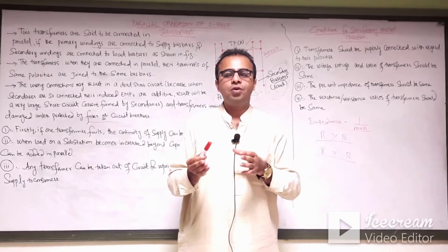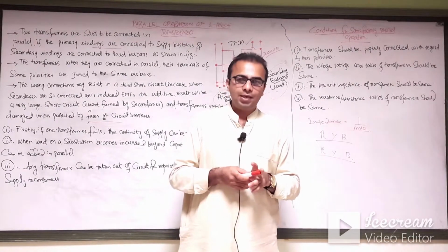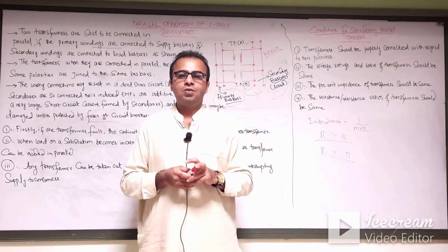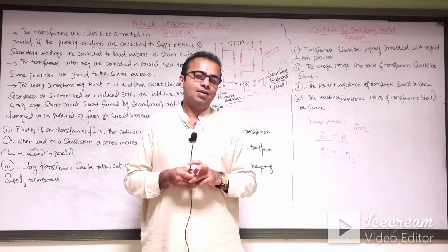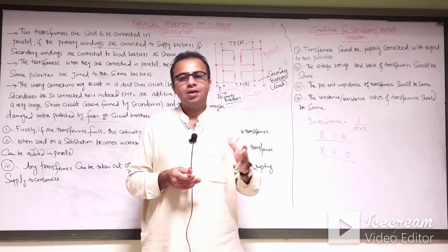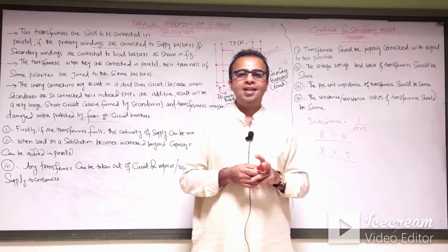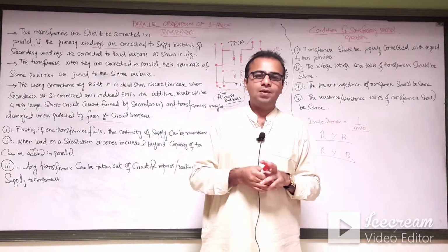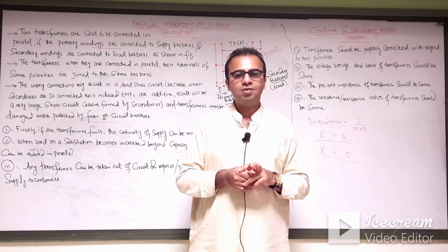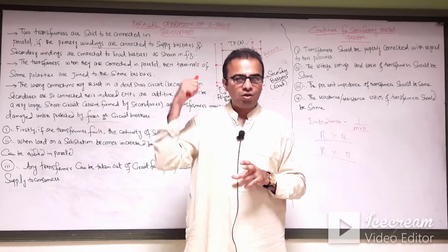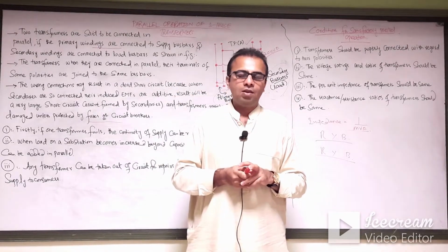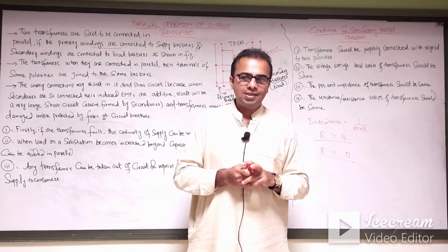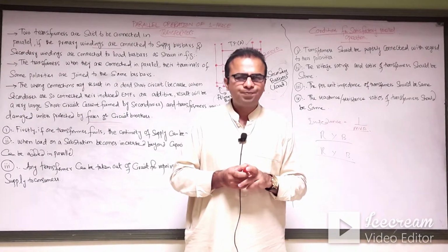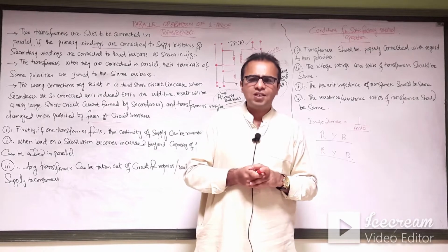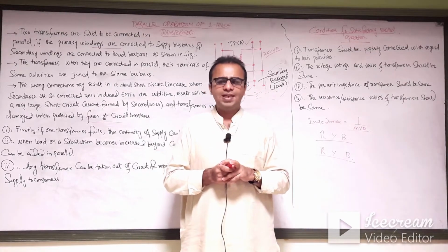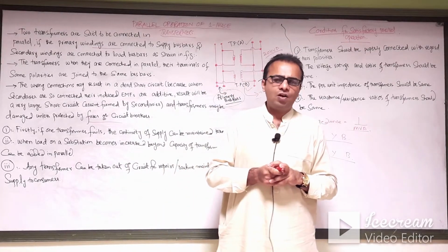When two or more transformers are connected in parallel, so that the primaries of both transformers are connected to the supply bus bars and the secondaries of both transformers are connected to the load bus bars or secondary bus bars, as you can see in the figure on the board, that is called the parallel operation of transformers.